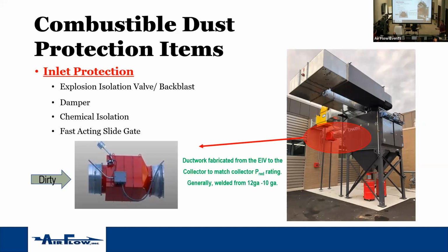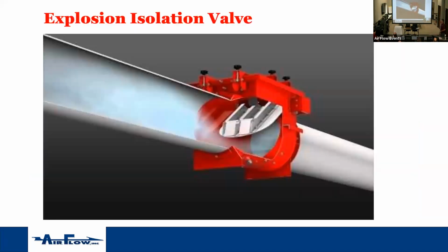because the explosion is allowed to come from a collector back to the EIV device itself, your ductwork from that collector to the EIV, that distance that's in between there, needs to match the PRAD rating of your collector. You don't want this section of ductwork to become the weakest point in the system and your collector to be protected and the EIV to stop it from going back into the building, but your ductwork to blow apart. It's an uncontrolled point where the explosion will leave that system. Usually that is, well, the ductwork between 12 gauge and 10 gauge, but that's a calculation you do based on what your PRAD rating is on your system, your collector.